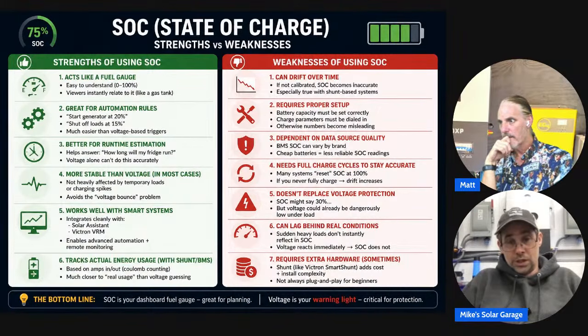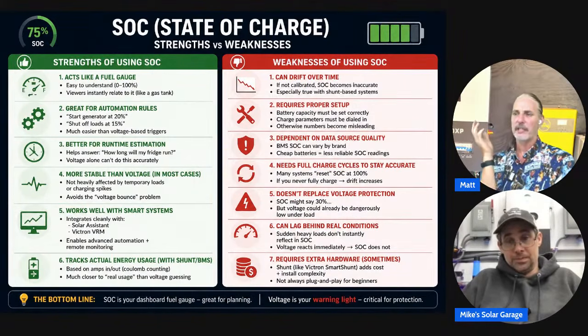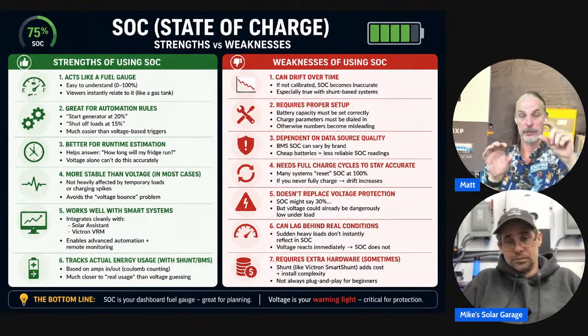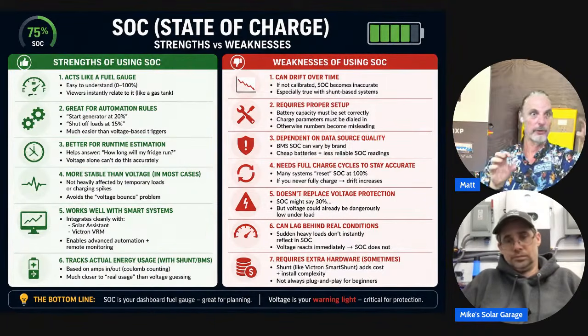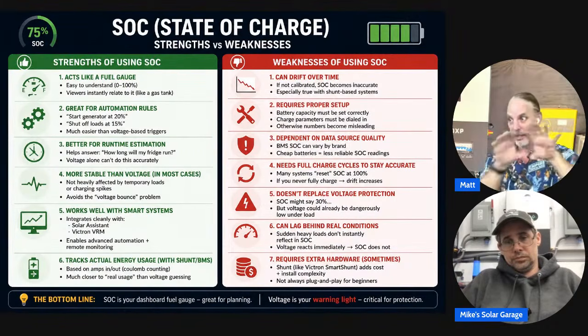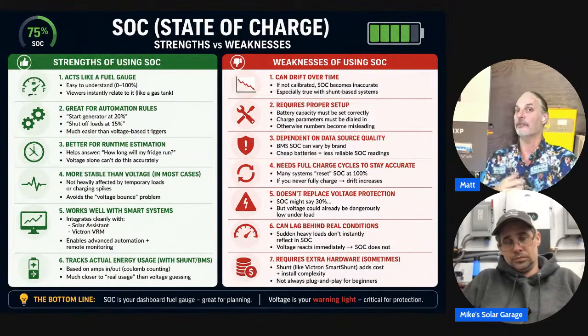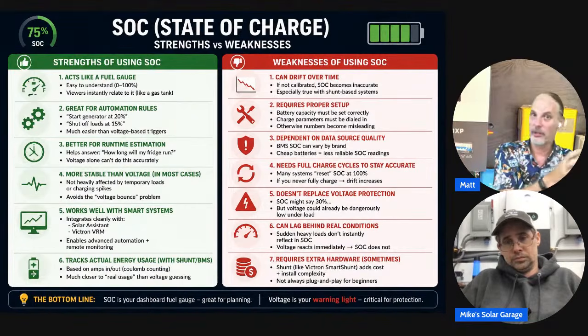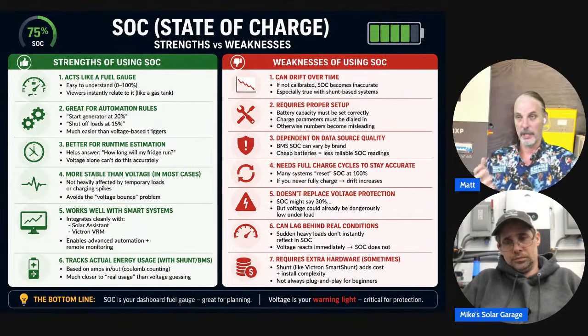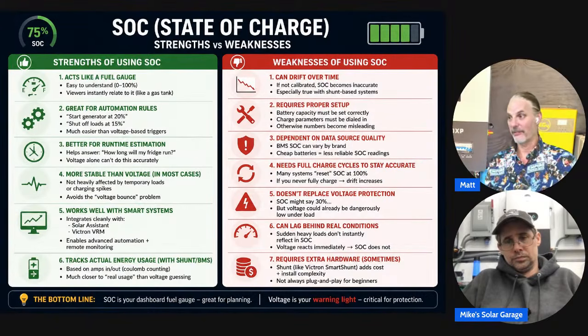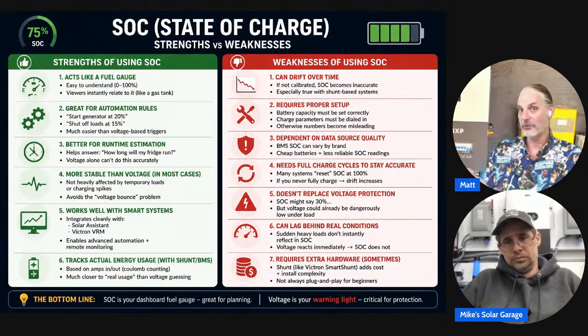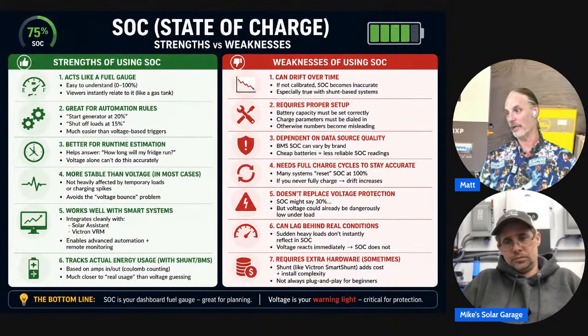So yeah, shunt, wiring, configuration — that takes time. A lot of times it sounds like a very easy thing to add a shunt, but what a lot of people don't realize is that means your batteries run to a bus bar, and then your bus bar runs to your shunt, on the negative side, and then your shunt runs across to another bus bar so you can hook devices to it. So you're talking about a lot of extra connections, and you have to be very careful to hook all your batteries to that bus bar and all your devices on that other bus bar. I've seen multiple times where people have one charger or one small DC device attached to the battery side of things, and they don't understand why their state of charge is off. That's because the constant charge or constant drain on the wrong side of that shunt doesn't get registered. So you're constantly becoming more and more inaccurate as time goes by.